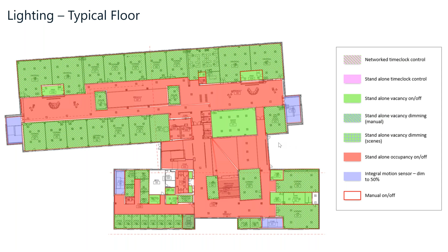That covered the majority of the building. We also have some spaces on standalone time clocks, and some with integral motion sensors that dim to 50%, like the stair towers or egress paths. We never let those go fully dark, but upon entry the lights increase from 50% to 100% for egress and communication—encouraging students to take the stairs instead of the elevator in a net zero energy building.